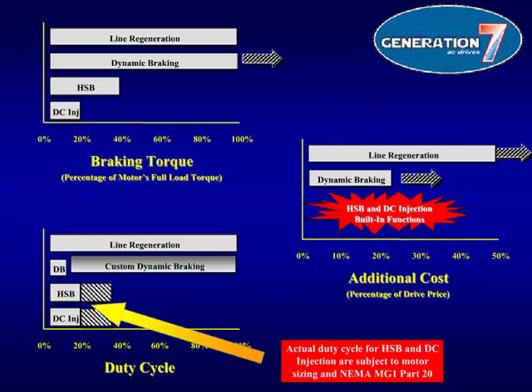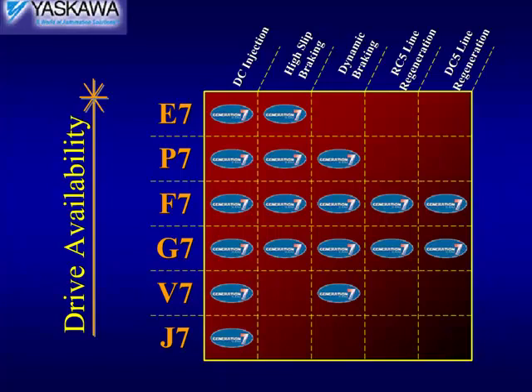Different drives have different braking method availabilities. This chart shows which braking methods are available in each drive. For high-end applications requiring line regeneration, only the F7 and G7 are equipped to handle the RC5 and DC5 regeneration modules. Dynamic braking is capable with the P7, F7, G7, and V7. DC injection is a built-in function available in all 7th generation drives. Once the braking method is determined, this chart, along with the control requirements of the application, will guide you in selecting the appropriate drive.